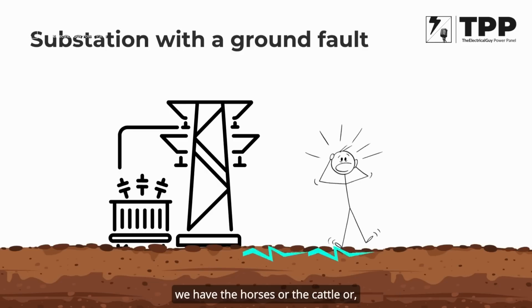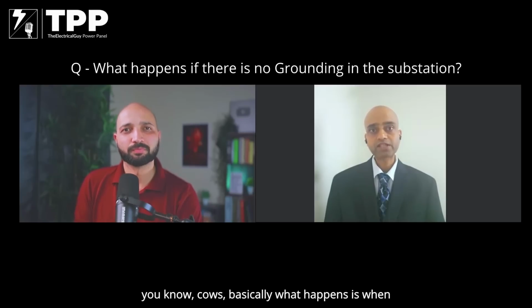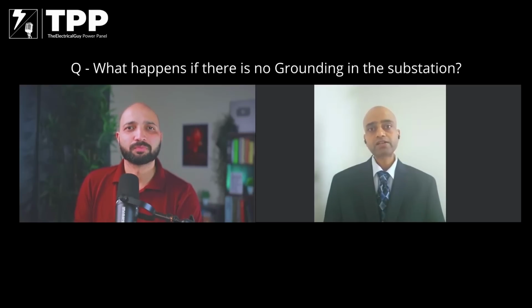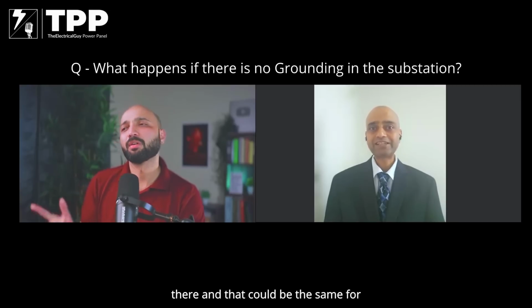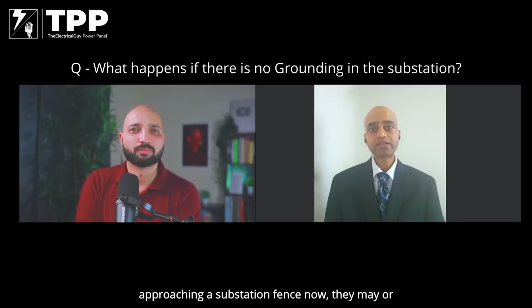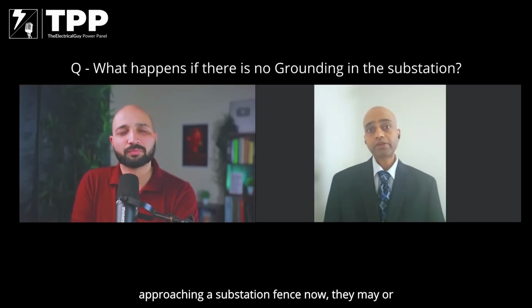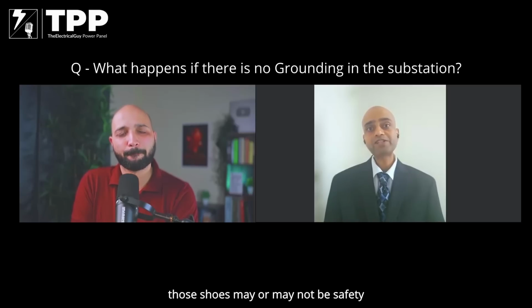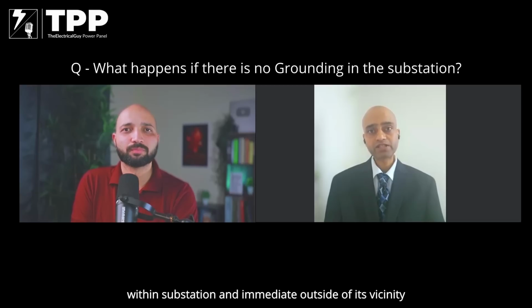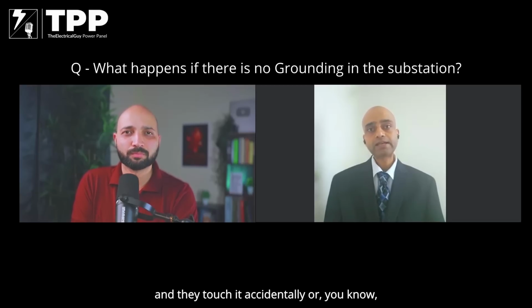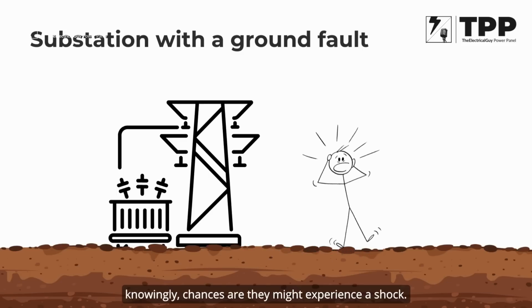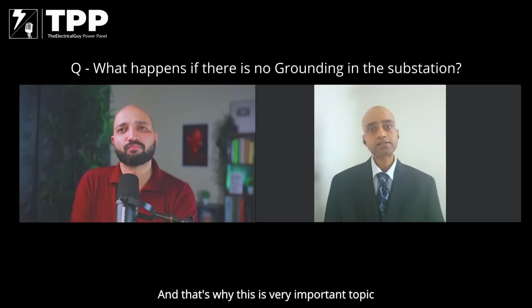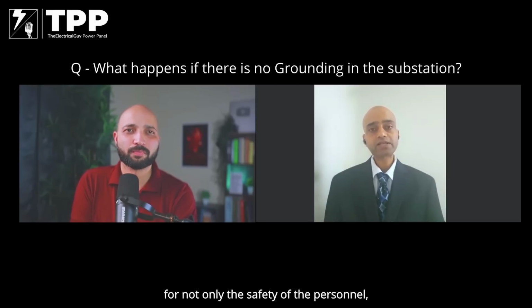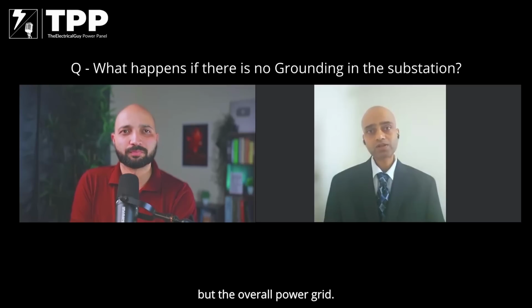A simple example could be horses or cattle, cows. When they come in contact with this GPR, their legs are at two different potentials, so basically we are having a short circuit there, and that could be the same for a person. If a person is approaching a substation fence, they may or may not have shoes on, and those shoes may or may not be safety shoes. Essentially, if a person is approaching a metallic portion or any metallic enclosure within the substation or immediately outside its vicinity, and they touch it accidentally or knowingly, chances are they might experience a shock. That's why this is a very important topic, and why grounding is very critical, not only for the safety of personnel but for the overall power grid.